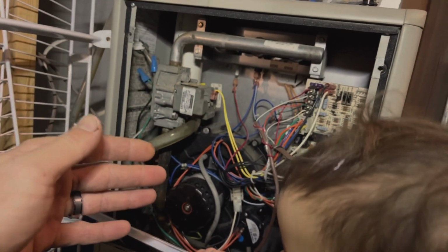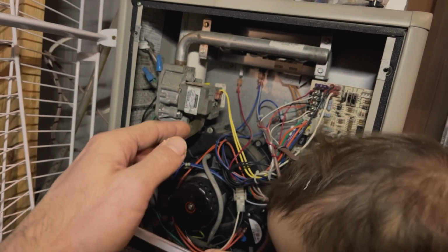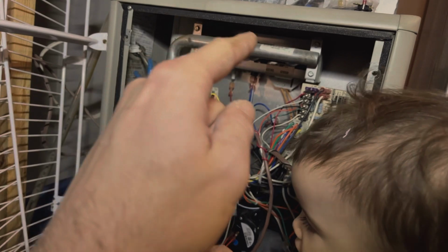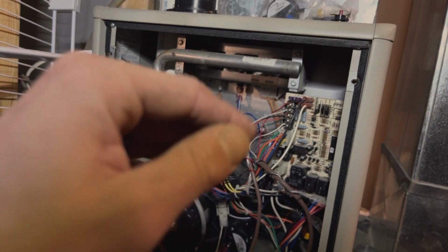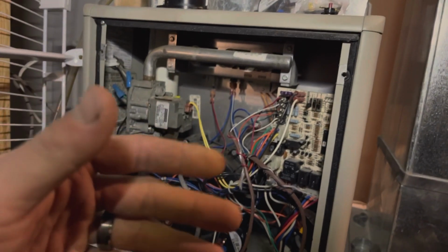So if the flame sensor is your issue, usually what will happen is it'll go through the whole sequence. Everything will start up. Your inducer motor will start up and everything. And the gas will go and it'll light. And then it'll shut off because it doesn't sense that there's a flame, or it thinks the flame's out. So I believe that that's when it's going to be your issue.